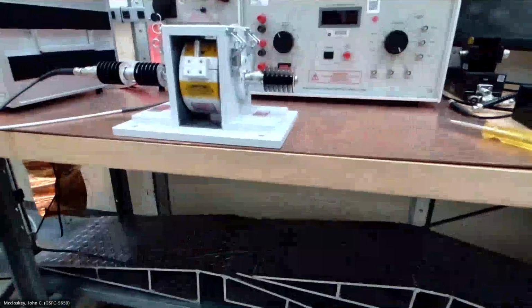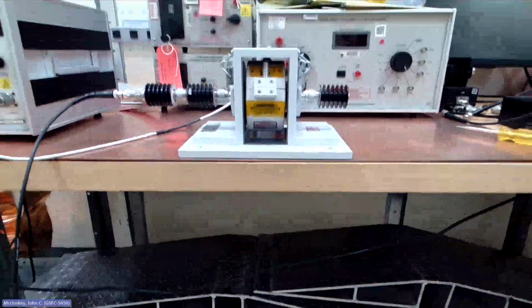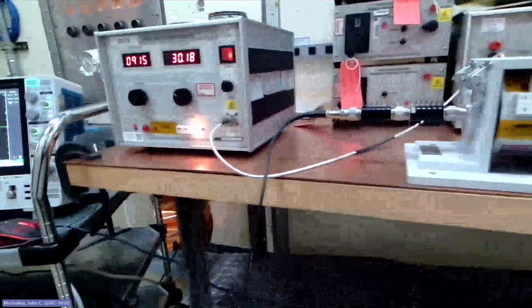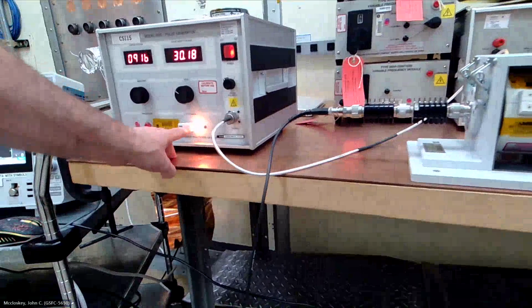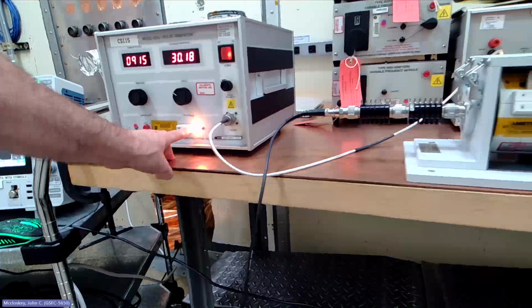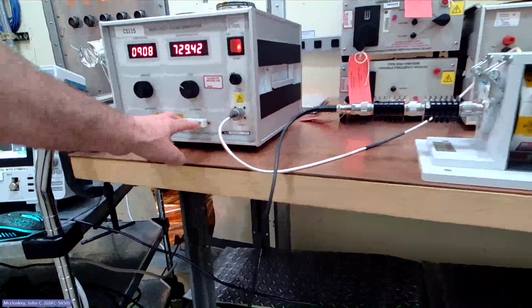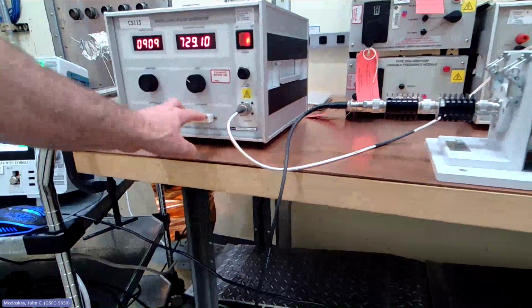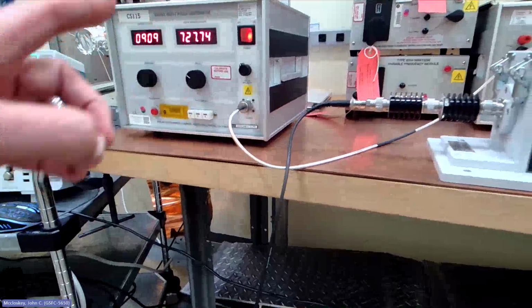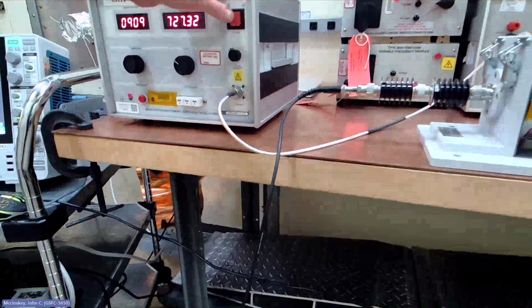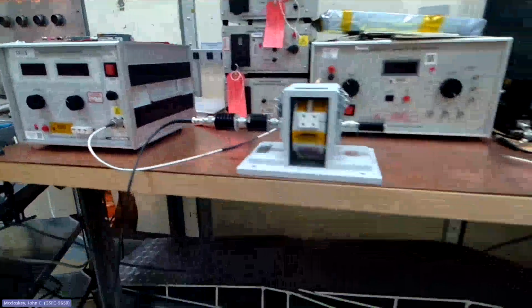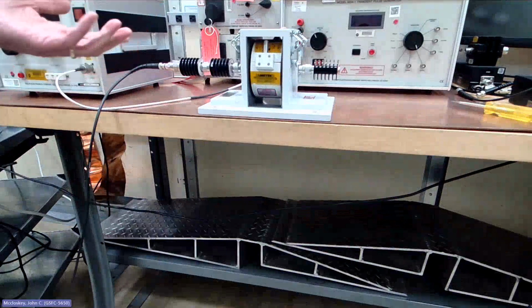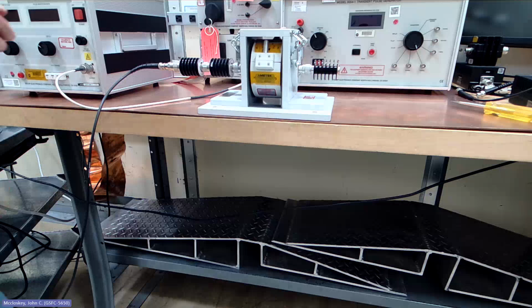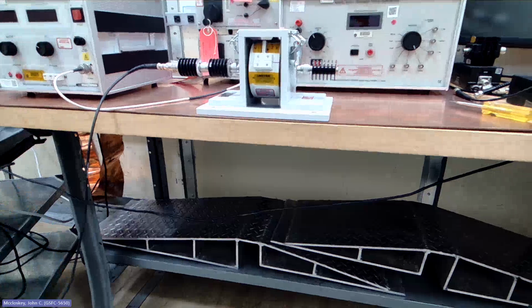Okay. So now, before we do anything else, we're going to disable the signal generator. I'm going to disable you. You can actually disable the output without turning the unit fully off just by hitting one of these band switches here, and so now the output's disabled. But for extra safety, I'm going to turn the unit fully off. You don't want it because that's 500 volts you're injecting. You don't really want to be messing around with it while you have an active signal going through it.